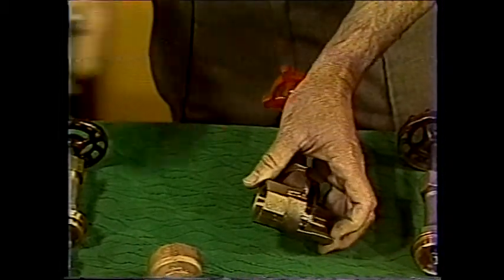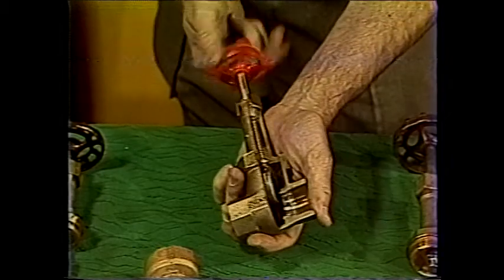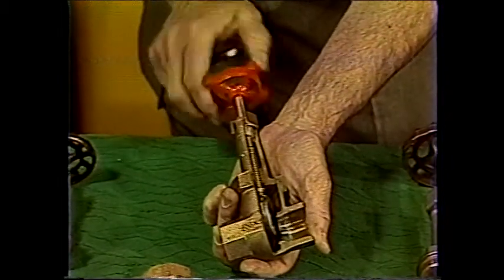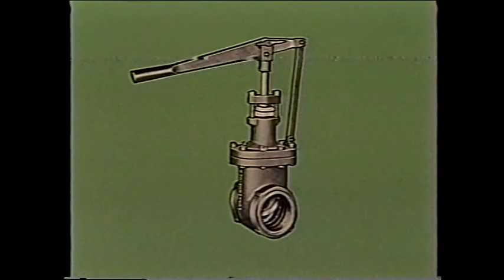As compared to some other valve types, the gate valve is slow in operation, since the hand wheel must be turned several times in order to open or close it. Gate valves are not recommended for throttling. Throttling is a term used when we use a valve to reduce either flow or pressure or both, but still allow some flow through the valve. Quick opening gate valves, like this one, are used in certain applications where speed of operations is of prime consideration. They take a relatively large force to open or close them.